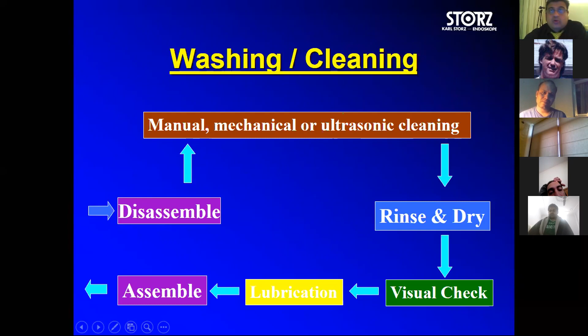So these are the protocols which should be followed, and the instrument has to be clean, and sterilization is no substitute for cleaning. Now, to have a healthy life of the equipment, this is the parameter which should be followed, but it is easier said than done. Theoretically, yes, the hardness of the water is defined, the chloride, the silicic acid, iron, manganese, copper, but at the end of the day, whatever water comes in your operation theater has to be used.